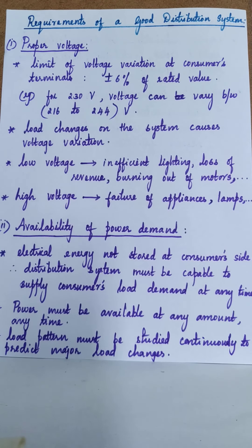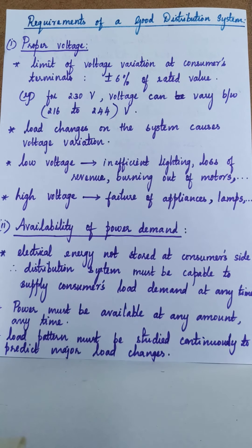Coming to the first requirement — proper voltage. At the consumer premises we need 230 volt, but this can be allowed to fluctuate within a safety limit of plus or minus 6%. So if the rated voltage is 230 volt, it can vary only between 216 volt at the lower end and 244 volt at the higher end. The main cause of this voltage variation is drastic changes in the load on the system.